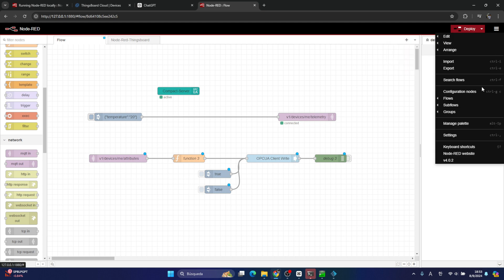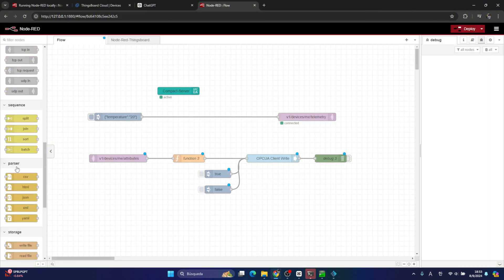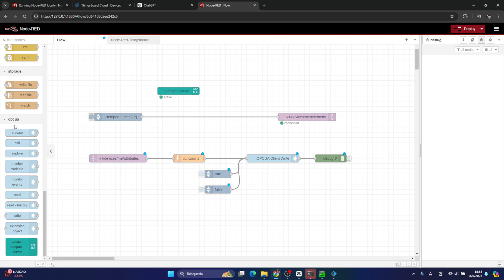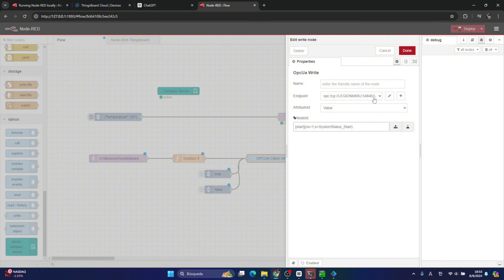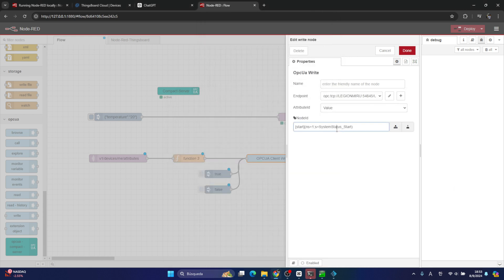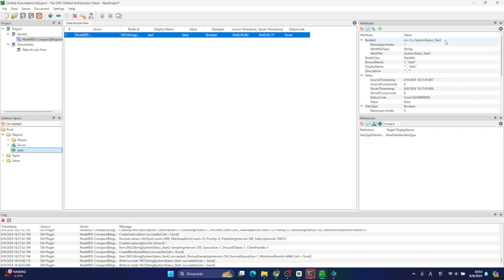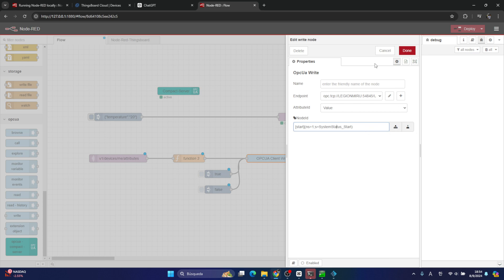To create the OPC UA Client node you will need to install the OPC UA for Node-RED library. After installing it, the OPC UA nodes will be available. Set the action to Write, then configure the endpoint — I'm using my OPC UA server endpoint. You also need to set the Node ID, which is the value you can see here in the properties section.